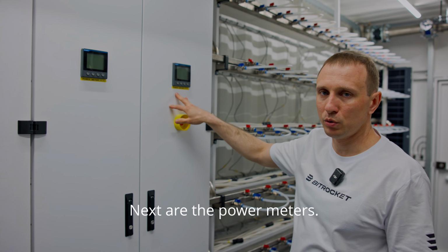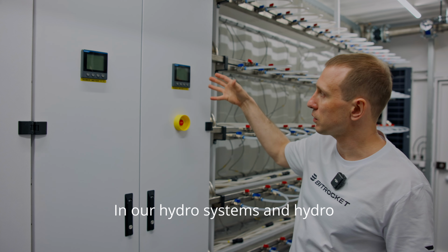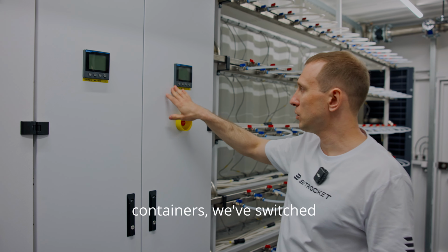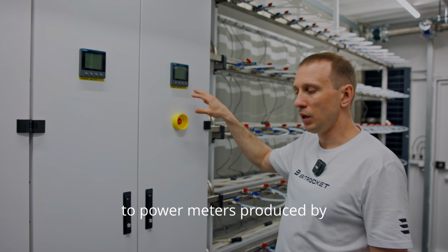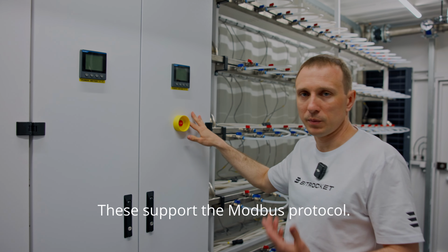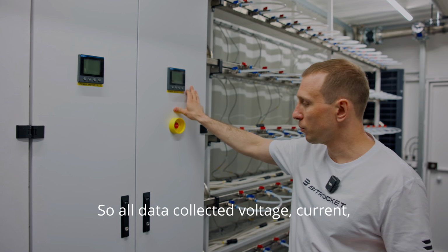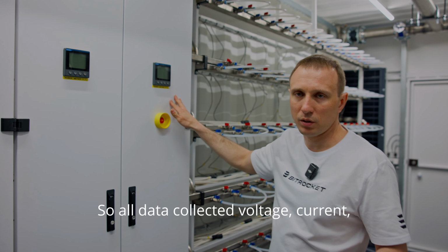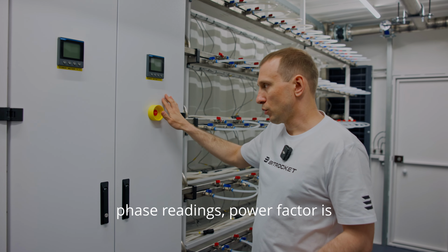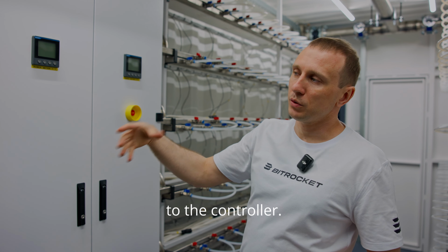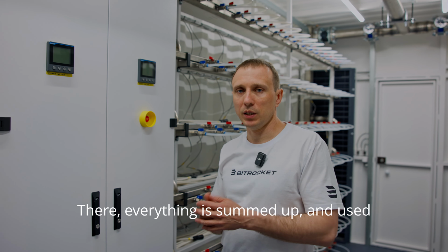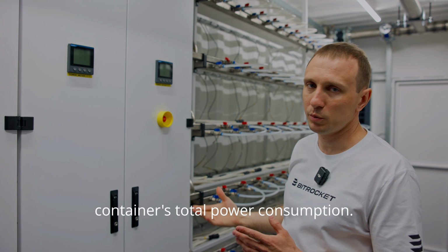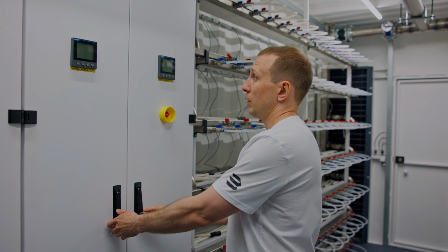Next are the power meters. In our Hydro systems and Hydro containers, we've switched to power meters produced by Chint. These support the Modbus protocol, so all data collected, voltage, current, phase readings, power factor, is transmitted directly to the controller. There, everything is summed up and used to calculate the container's total power consumption.